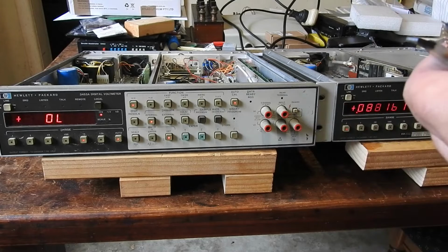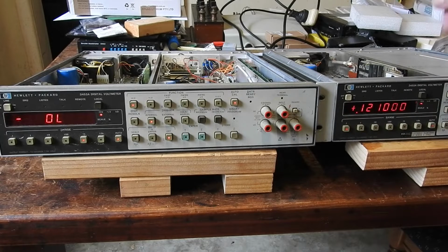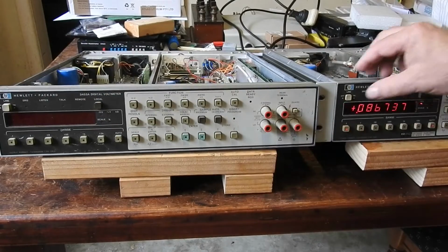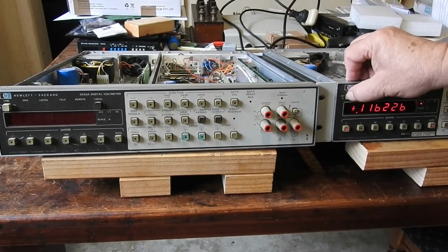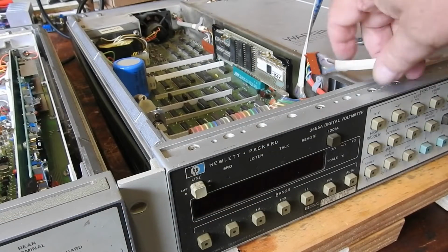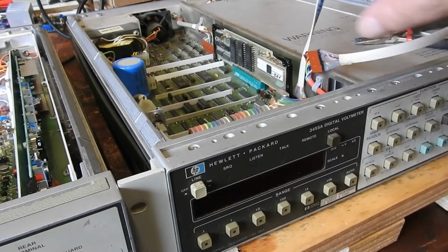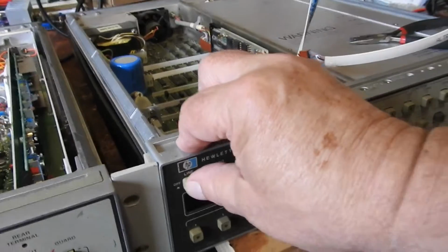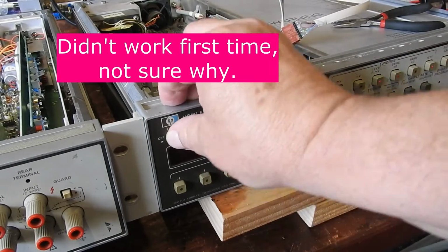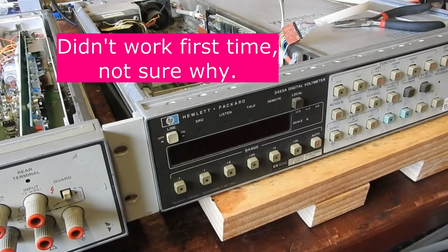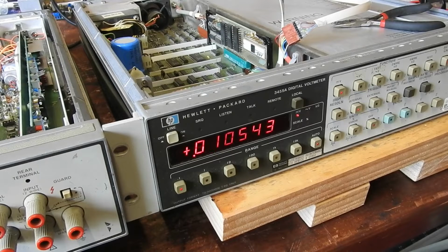But hopefully it works. So to verify that, I'm going to put it in the good meter, make sure that the good meter stays good with this. So I'll do that. Turn that off. Power switch on this has got a bit dicky. Right, there's my service cable, and if that's good, this meter should still work. I can't see anything wrong with the cable. No. Alright, so that's good. Now we'll try half splitting.